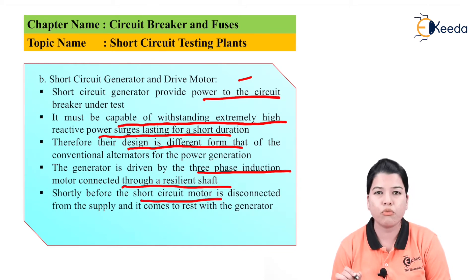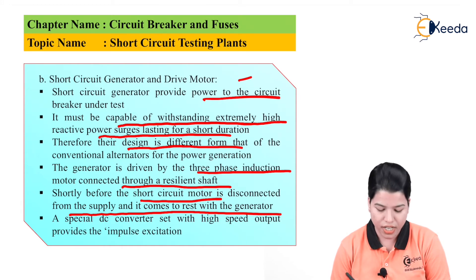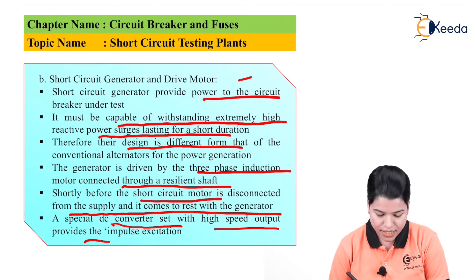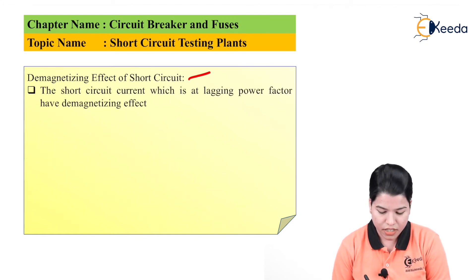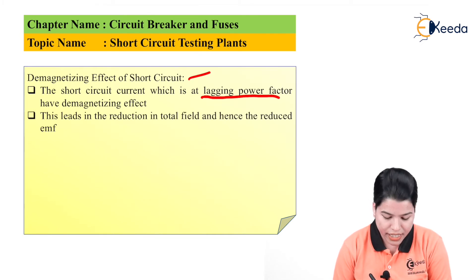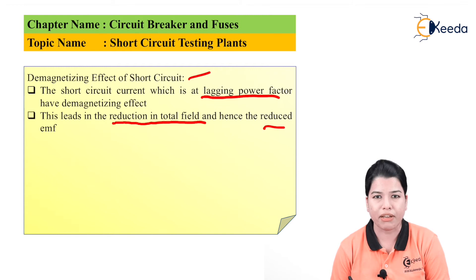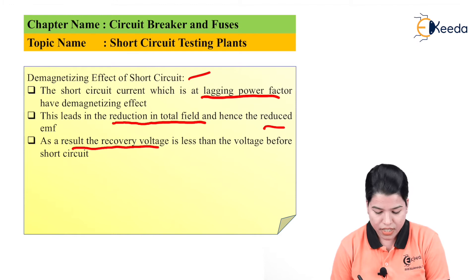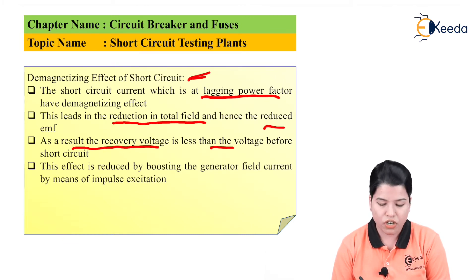Shortly before the short circuit, the motor is disconnected from the supply and comes to rest with the generator. A special DC converter set with high-speed output — called impulse excitation — is provided. The short circuit current at lagging power factor has a demagnetizing effect, reducing flux, the total field, and hence the EMF, so that the recovery voltage is less than the voltage before the short circuit. This demagnetizing effect is reduced by boosting the generator field current using impulse excitation.